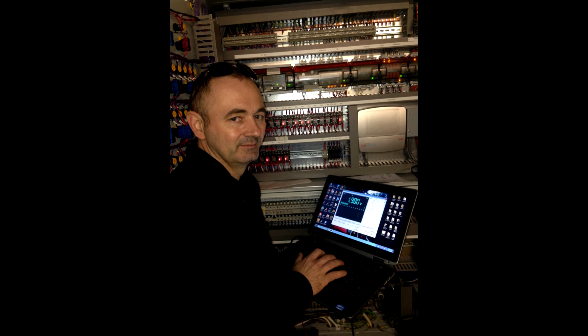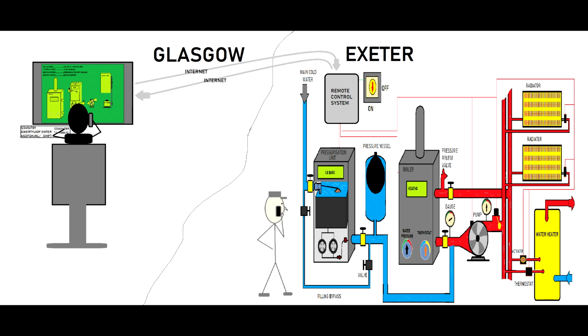If the unit is faulty, it should be integrated that way, so that the engineer who remotely monitors the system will see it. So again, the engineer turns up on the spot and says, oh, hello, I'm the engineer on call. I just want to let you know that the pressurization unit is not working. How is it not working? Because I can see on my computer it is working. I said, no, it is not working because I'm here and I can see it. It is not. There's a malfunction with this unit, and the circuit breakers interrupt the circuit. Oh, that is impossible because I can see the unit is enabled. So the guy who monitors the system remotely might not even know. He's not aware of the integration problems.